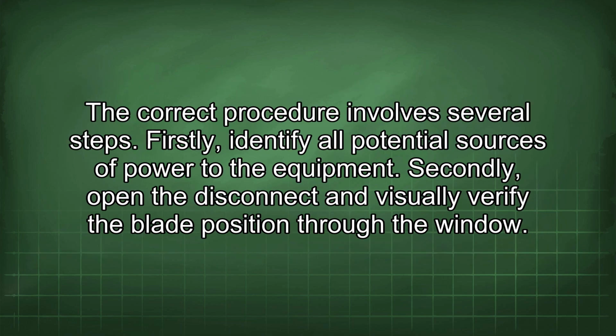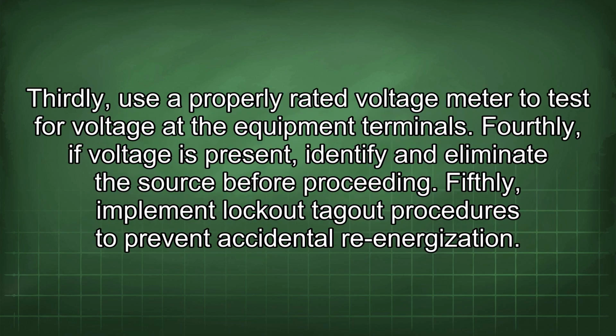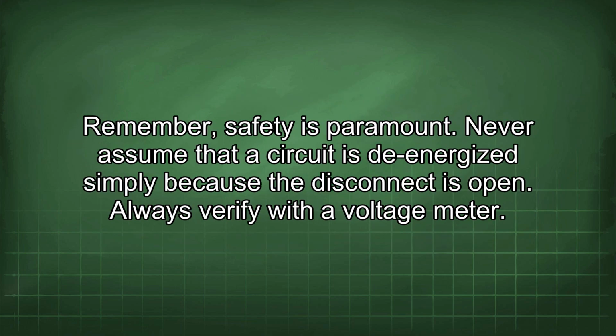The correct procedure involves several steps. Firstly, identify all potential sources of power to the equipment. Secondly, open the disconnect and visually verify the blade position through the window. Thirdly, use a properly rated voltage meter to test for voltage at the equipment terminals. Fourthly, if voltage is present, identify and eliminate the source before proceeding. Fifthly, implement lockout-tagout procedures to prevent accidental re-energization. Remember, safety is paramount. Never assume that the circuit is de-energized simply because the disconnect is open.